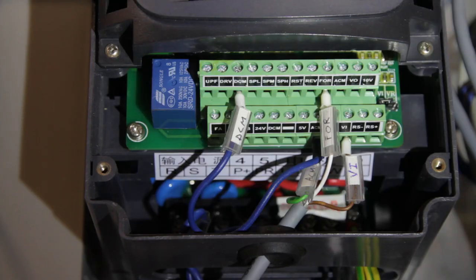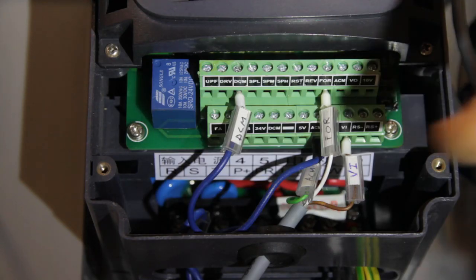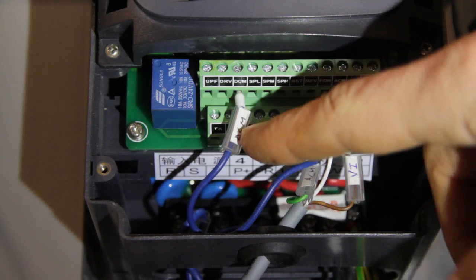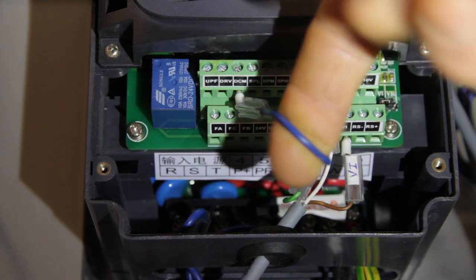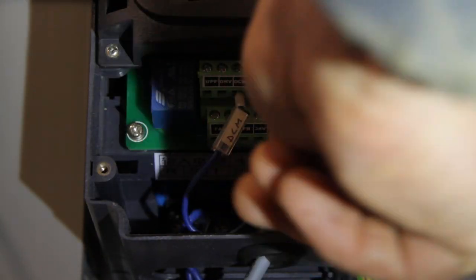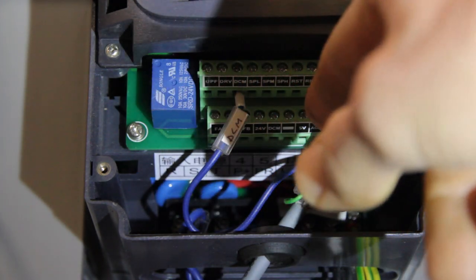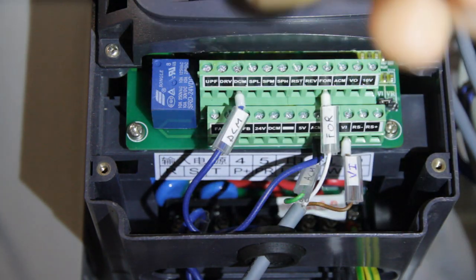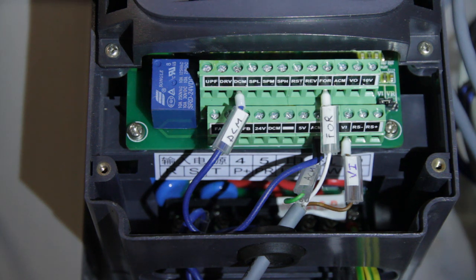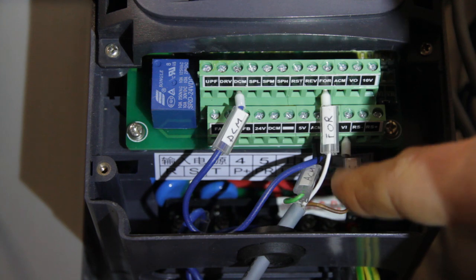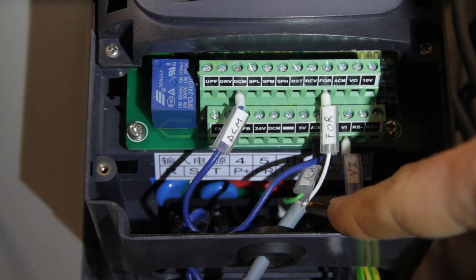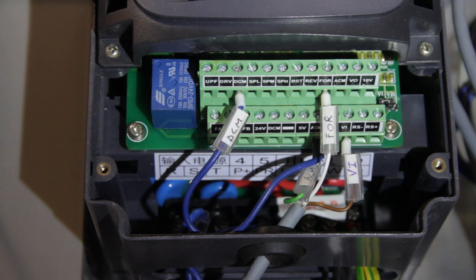The connections for the controls for the VFD are pretty straightforward. There is a digital common which needs to be connected to the analog common, so you can see this is connected. And then there is a forward signal which is connected to the forward, which is used to turn on the VFD. And then there is a voltage in which is analog input, which comes from the analog output to control the speed of the VFD.